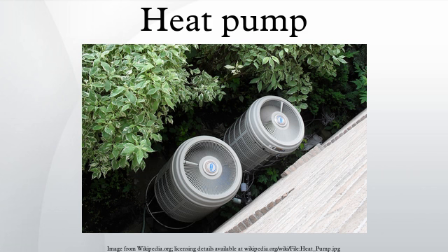Heat pumps are more effective for heating than for cooling an interior space if the temperature differential is held equal. This is because the compressor's input energy is also converted to useful heat when in heating mode, and is discharged along with the transported heat via the condenser to the interior space. But for cooling, the condenser is normally outdoors, and the compressor's dissipated work must also be transported to outdoors using more input energy, rather than being put to a useful purpose.